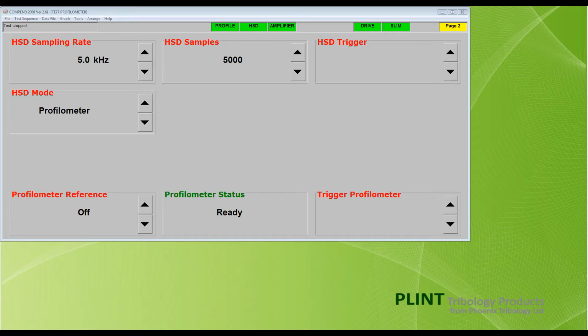Setting the trigger Profilometer box to measure will trigger the surface measurement routine under manual control, as long as the reciprocating head is fully retracted. Manual triggering is only ever used during setup and calibration. Triggering within a test sequence automatically retracts the moving specimen carrier to the end of the stroke before executing a surface measurement cycle. It makes sense to use a test sequence, as multiple measurements taken over a long period of time will provide the most useful information.